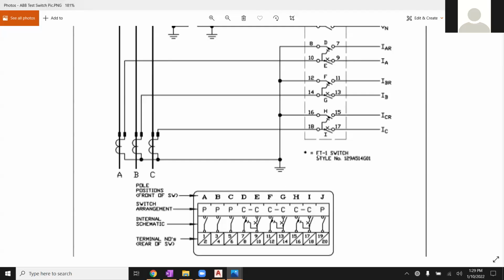Yeah, so let's say if I open up the E 10-9 and I don't open up the D part, it still has shorted the A phase. Yes, exactly. If you open one or the other or both, they are going to be shorted properly. You can't guarantee that you're going to truly open both at the exact same moment. So as soon as you open one of them, or even in the process of it opening, it's going to short before it's fully open. It's a make before break test switch. Good point. Thanks.